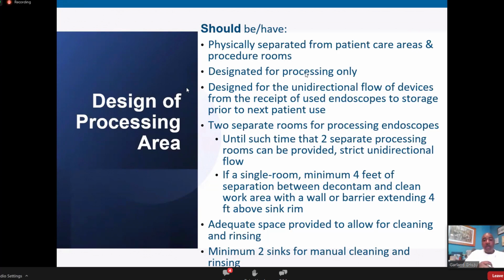If you have a single room, some folks didn't know that you need a minimum of 4 feet of separation between the decontam sink and where your high level disinfection or other area is. So I've seen some areas with a wall, some folks have had plexiglass put up by their engineering department.